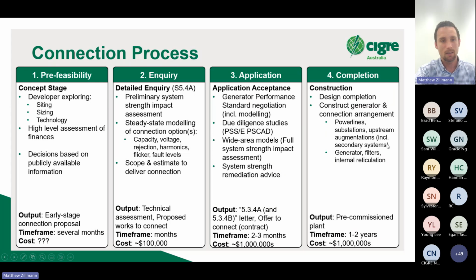One thing often overlooked is the secondary system. Maybe more so a distribution challenge, but a lot of these connections are in areas that weren't originally built to take multi-megawatt or tens-of-megawatt generators. So there's often major investment in secondary systems, namely protection. Then on the generator side, they have to actually build the generator and an ability to receive and reticulate electricity around their network.